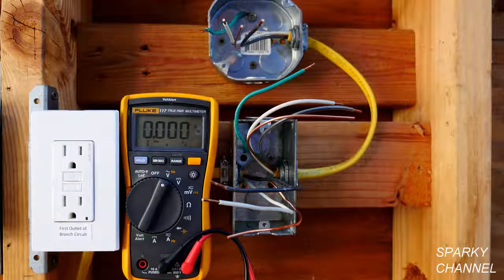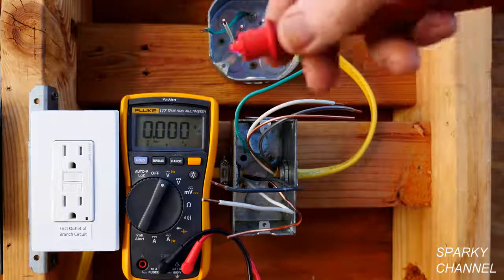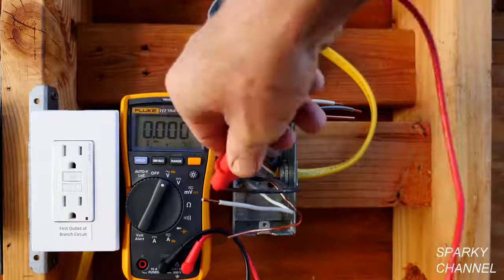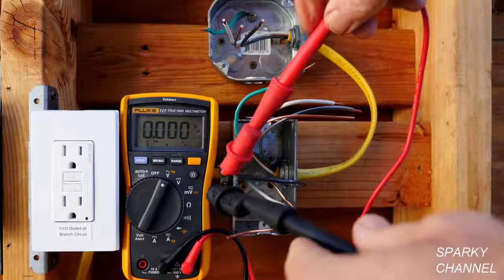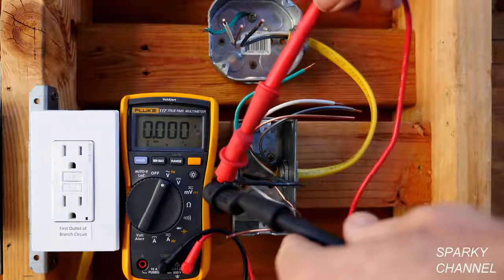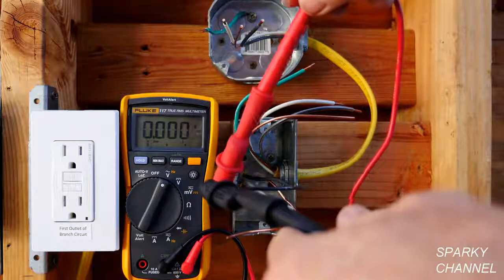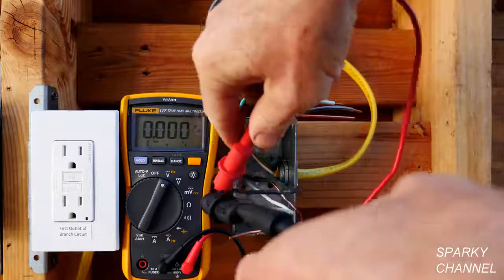Now I have turned off the circuit breaker, and I have removed the Wago lever nuts, and I'm going to do a quick test just to make sure that the electricity is off. I'll put my leads on the hot and the neutral that were showing 121 volts earlier, and we have 0.0. So the electricity is indeed off.